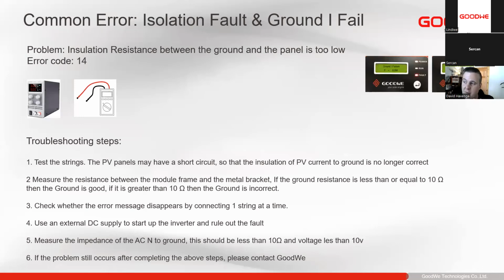If we're testing with the modules, and regardless of our modules we tested in the inverter, we're still getting the isolation fault, we can also start up a DC power supply, see if with the DC power supply we also have an isolation fault. If it still remains there with the DC power supply, we can be sure to replace the inverter for you. Unfortunately, it does happen. Lightning may strike or anything might happen, and then a component might fail. So sometimes you will get an isolation fault if one of the internal components has failed as well.